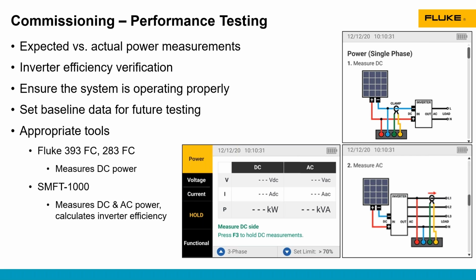And you need to ensure that you can get all the negative conductors into that clamp on the DC side. So if you had a combiner box like we saw a couple slides ago, that may be challenging with that quantity of circuits there, although that would probably exceed the 60 amp rating anyway. The Fluke 393 and upcoming 283 multimeter are also capable of measuring DC power. You would have to measure AC voltage and current separately and calculate AC power and then do the math between those to get that performance data if that's what you were looking for.